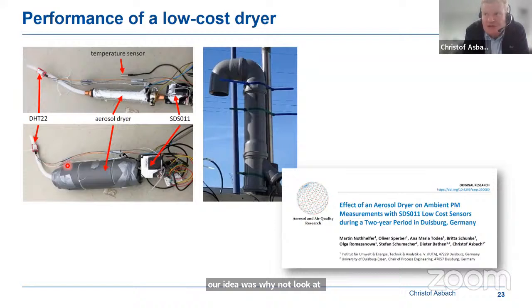In fact, that's what the scientific grade instruments, like the FIDAs, for example, also do. They use a dryer, in their case not a low-cost dryer, but a much more expensive dryer. And these dryers cost something like a few €1,000. And of course, you don't want to use a dryer for a few €1,000 to operate a €50 sensor.